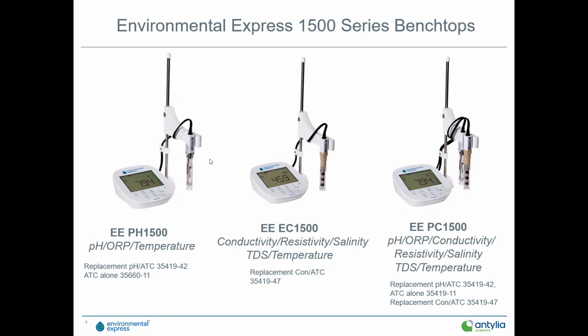In that case, if your customer's got a favorite pH electrode, maybe they have a high-end electrode that they really like to use, or it's an application specific electrode and they want to use that, by purchasing our ATC. We have a separate ATC probe for these meters. They could use that ATC and literally use any pH electrode with a BNC connector on it. Allows that customer that flexibility to choose and keep the sensors that they like or that they feel confident in.